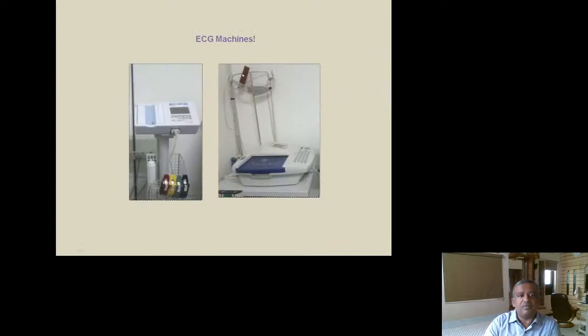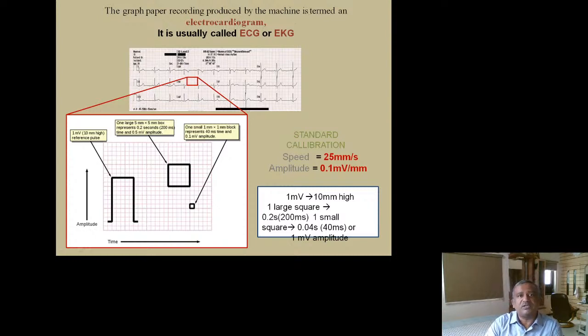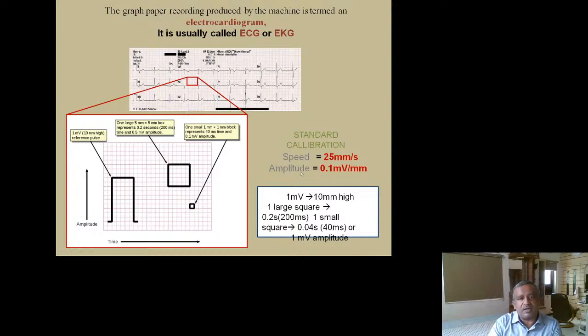The electrocardiograph is the machine, and the electrocardiogram is the tracing it produces — we call it ECG or EKG. Modern machines are computerized and measure PR interval, QRS, and QT interval. On the graph paper, one millivolt deflection equals 10 mm, one large square equals 0.2 seconds, and one small square equals 0.04 seconds. Normal recording speed is 25 mm per second, and amplitude is 0.1 mV per mm.